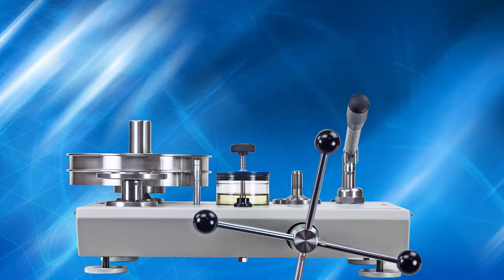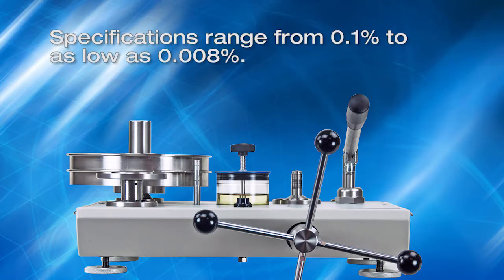Deadweight testers available on the market today have specifications from 0.1% to as low as 0.008%. As we have already mentioned, accounting for all variables and performing a full calculation of pressure allows for the best uncertainty possible. But at what point is it necessary?